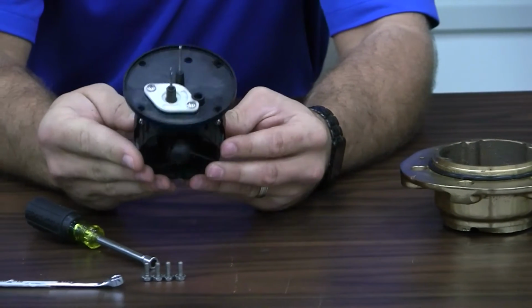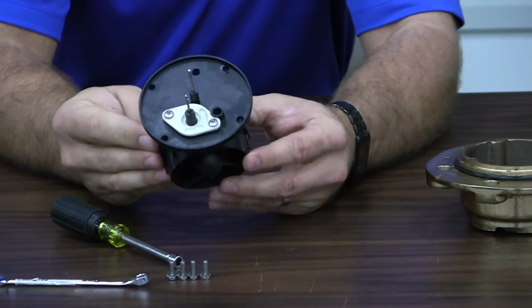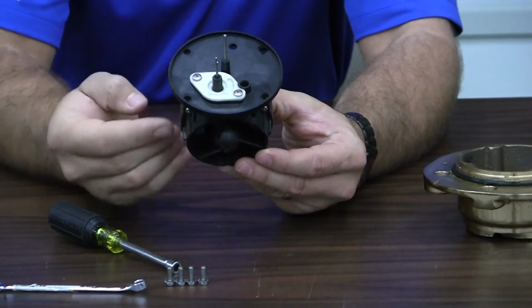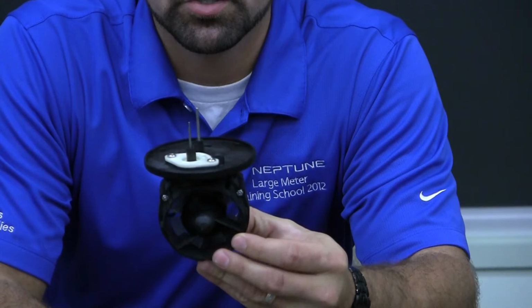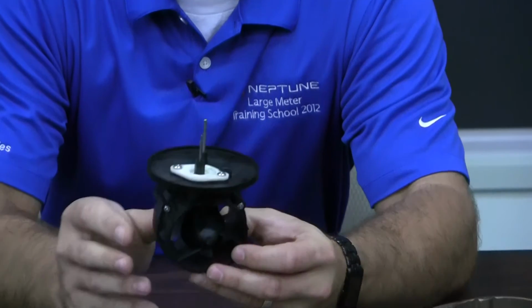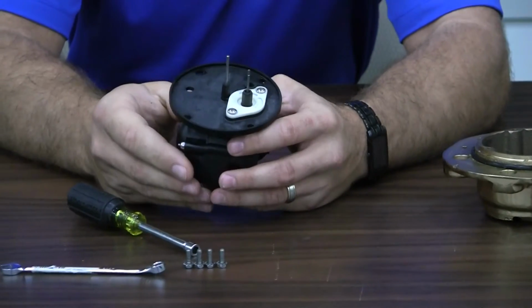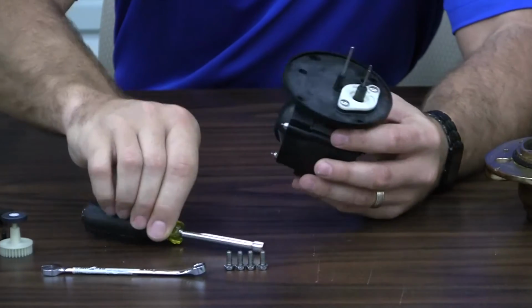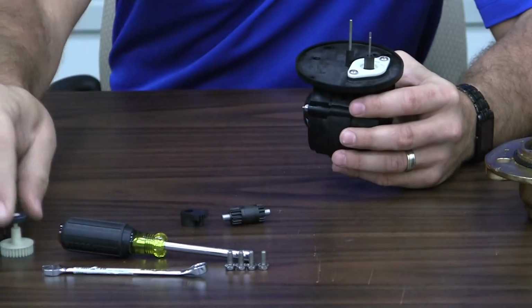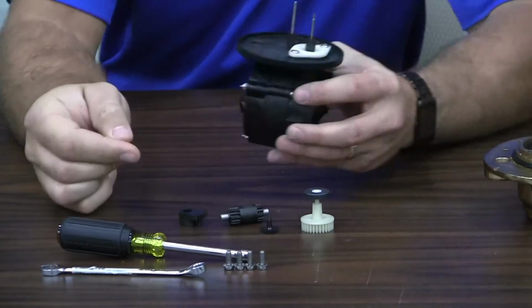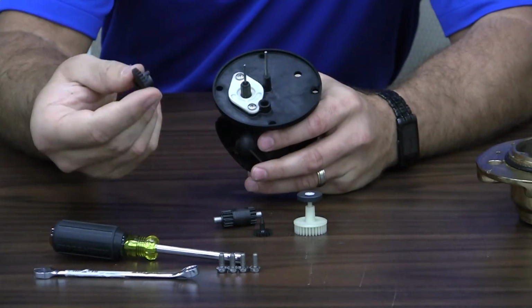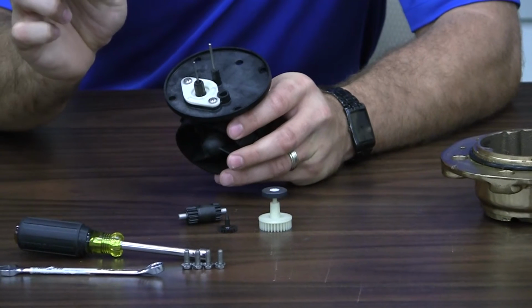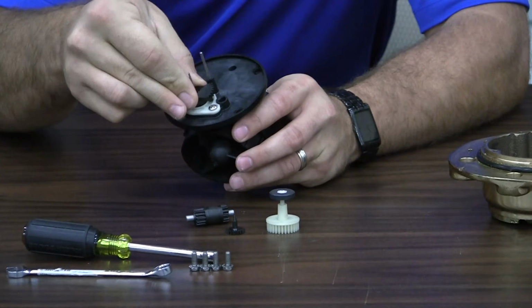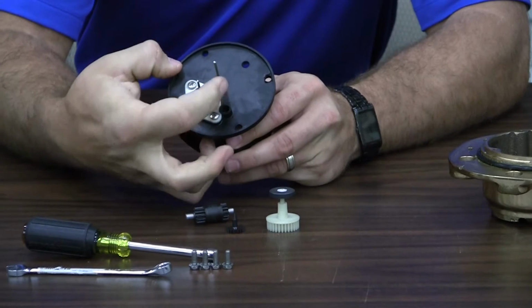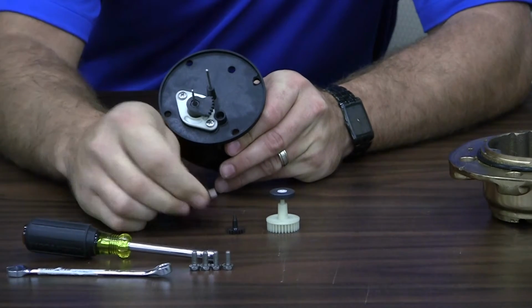To make sure the turbine hasn't bound up by any means, or if you've got it together correctly, I'm going to blow through the turbine and make sure that it spins freely and it comes to a smooth stop. As you can see, the turbine's spinning and it comes to a nice smooth stop. Now we're ready to put our gears back on top of the turbine element. We have 4 gears, as you remember taking them off: our calibration gear, our foot gear, our magnet gear, and our drive pinion gear. To start with, we're going to take our foot gear, and there's a slot and a little post that we're going to make sure that it lines up.